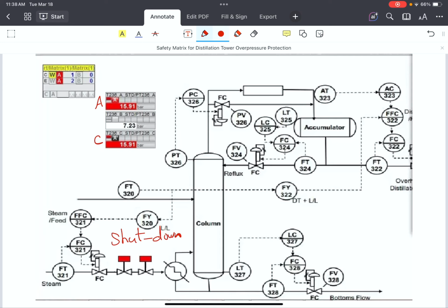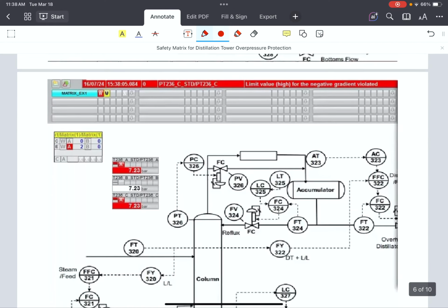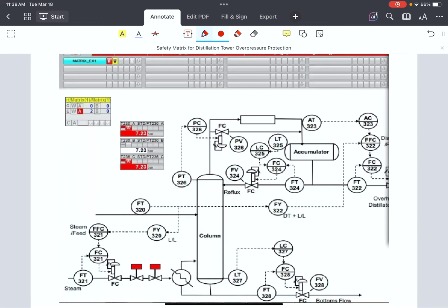After a while, everything is getting back to normal. In the next slide, the pressures are getting less than the violation range, but the valves are not operating because we decided based on the safety requirements that in order to energize the valves, we need operator intervention.